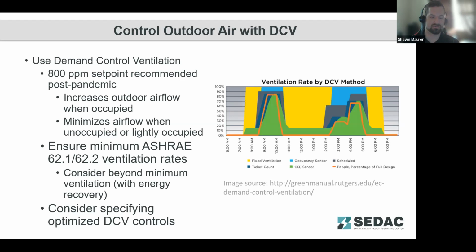The problem runs across where buildings are designed for those ventilation rates, but they don't actually achieve them. Poor duct runs and things on exhaust fans reduce their exhaust rates. Unbalanced air flows out of ventilation systems can reduce ventilation rates in spaces. So having a proper HVAC commissioning process in place to ensure that you've designed for these ventilation rates, you're actually achieving them, is also very important, not just for indoor air quality and maintaining the health and safety of occupants in your building, but also for the proper sizing of that equipment.